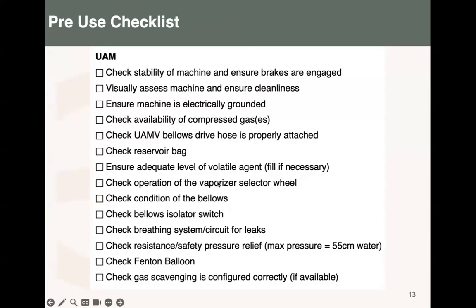So on the UAM, you check for stability, cleaning, electrical grounding, and availability of the compressed gas. Remember, compressed gas is a backup. It's for emergency. That's why I advise having at least one. I've gone to so many places where there are so few of them, and they don't always keep the backup compressed gas. But we advise it, and that's why you have to check and make sure not only that you have a cylinder, but also that it has oxygen.